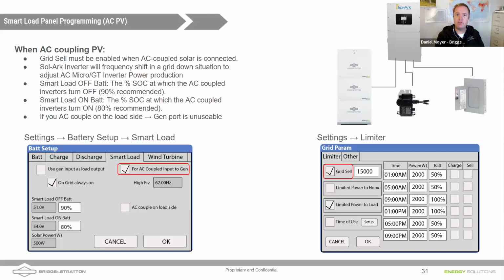It's not like a charge controller. Yeah, and remember that microinverters are trying to kick out as much power as they can off the solar panels. They're really trying to produce full power and push that somewhere. And if there's nowhere for that energy to go, we need to be able to push that energy into the batteries. If the batteries are full, there's nowhere for those microinverters to send power if the grid is down. And so that would shut the microinverters off and prevent overcharging the batteries. And that extra 10% that we're leaving there, if you have a really big battery bank, you could bring that number up to 95%.